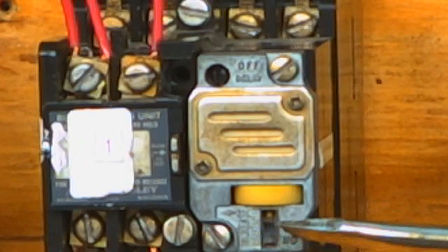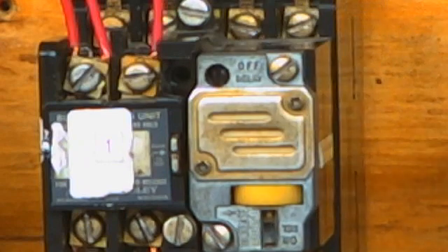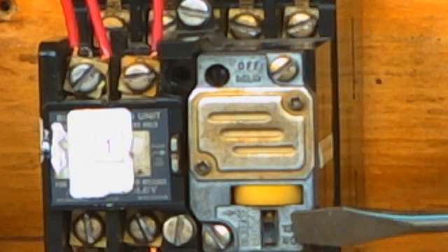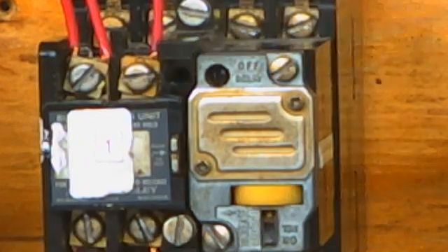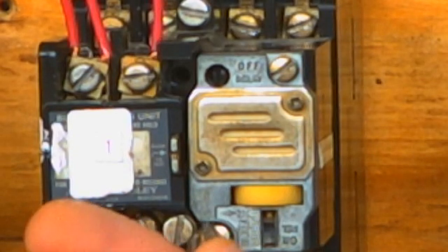So if I take this thing out, take these two screws out and flip it upside down, this thing will now be right side up. Now it says on delay. It all happens because of the mechanism that's behind here. You guys are welcome to take this thing apart and see how it operates. So I don't even have to move the wires around. I just have to change this thing out to make it an on delay.